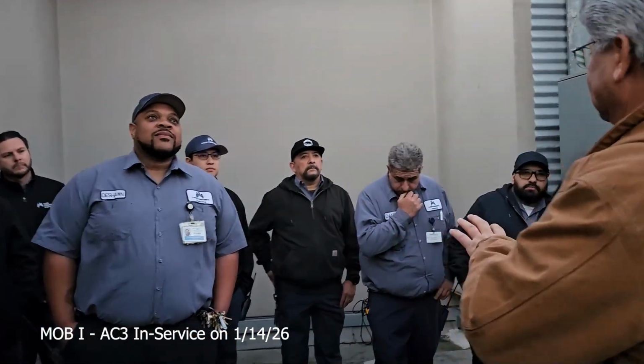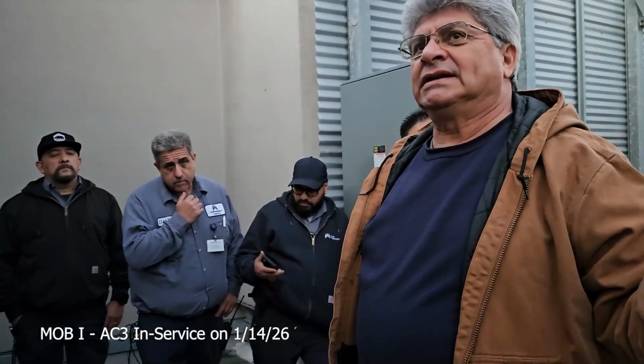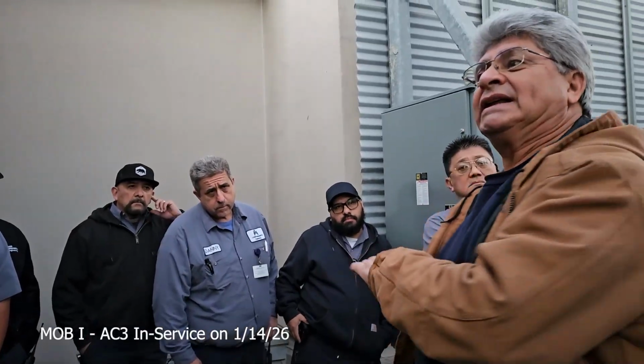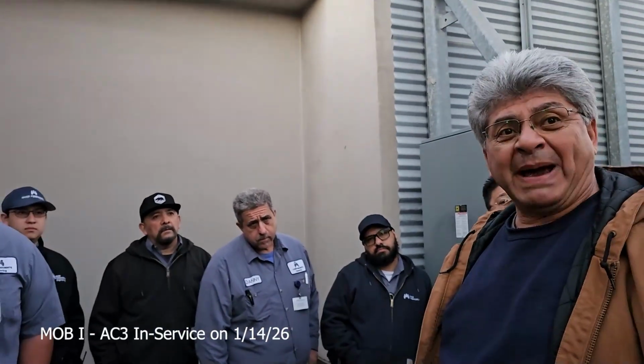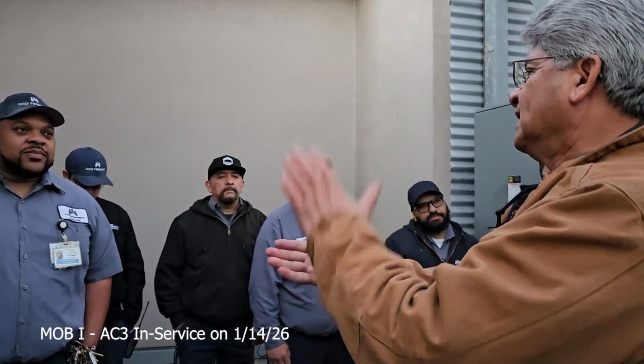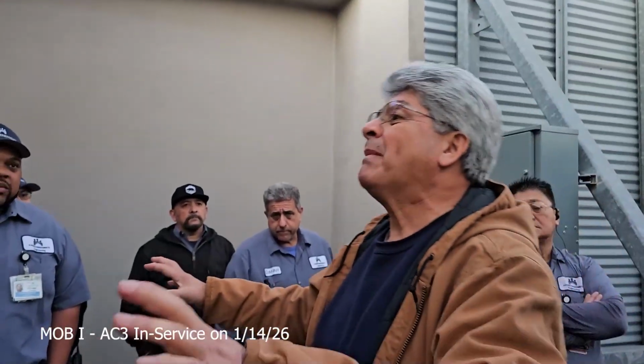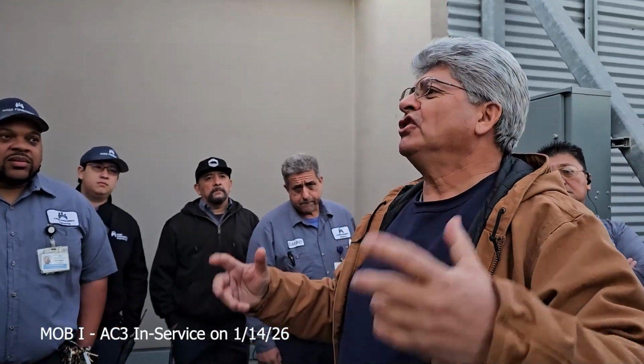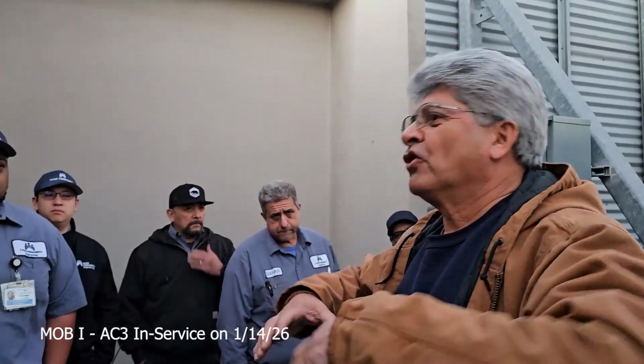So here's something interesting. If she shuts down at like 9:20, they shut down. When this machine is at a dead stop and it goes to start back up again, it takes a while to build your static. You all understand how that operates, right? If anybody needs me to... Yeah, why don't you go ahead and explain that? Okay, great. You all have a VAV system in your building. So let's say it's warm out. This machine stops. Your set point is 51 degrees. When she turns on, all your VAV boxes are going to be calling for cooling, so all their dampers are wide open.